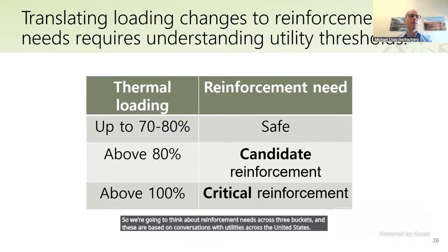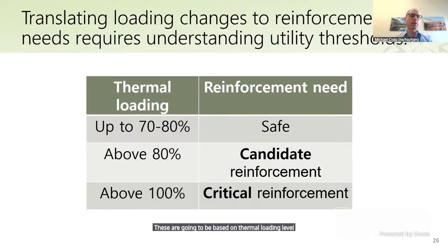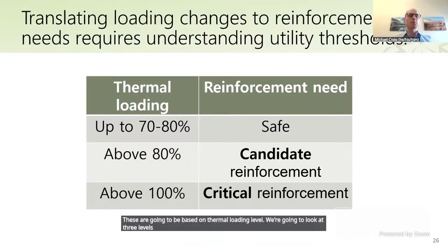These buckets are based on thermal loading level, and we'll look at three levels. If you're up to 70 or 80%, depending on whether it's a line or a transformer, you don't need to reinforce—you're in a good operating regime and not worried about it, so you just sit on it.